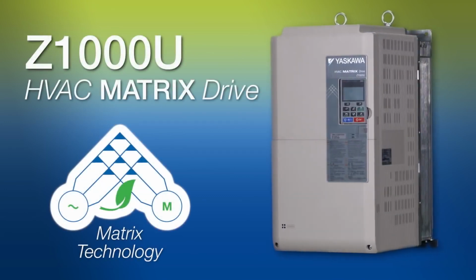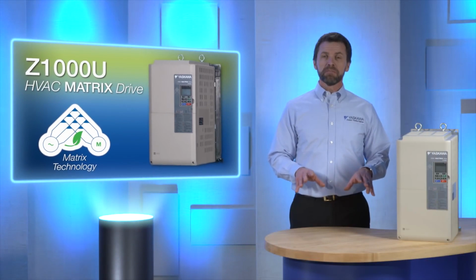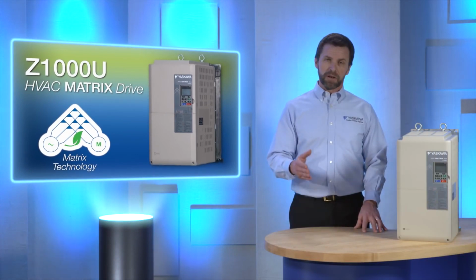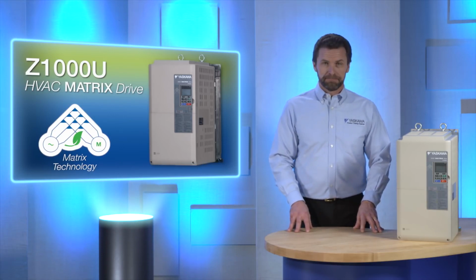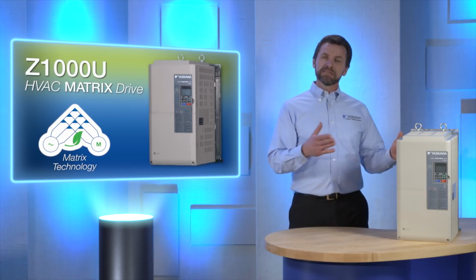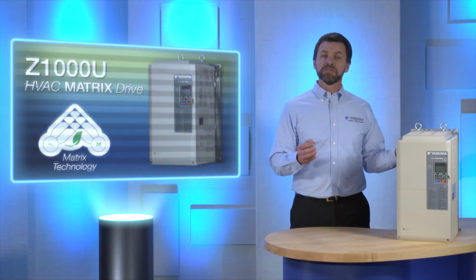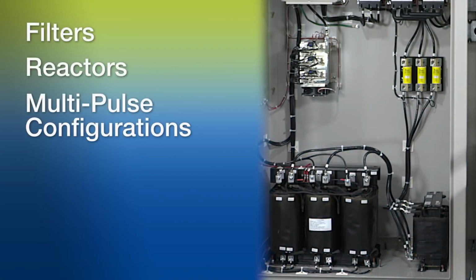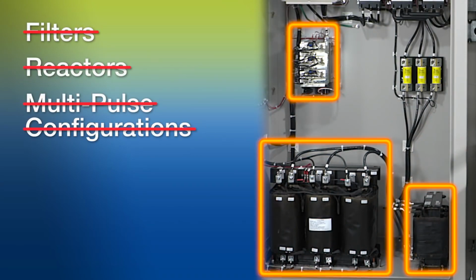Matrix technology offers significant energy savings by returning the motor's regenerative energy to the power supply without having to connect any special device. Energy use is minimized with no waste across bleeder resistors or large magnetics such as transformers and reactors. The Z1000U can instantly display the power usage and money saved with a series of customized monitors. Another significant benefit of the Z1000U is its compact size relative to today's commonly accepted package solutions. Because you don't need external devices such as filters, reactors, and multi-pulse configurations to mitigate harmonics, you can construct your system even when there's limited space available.